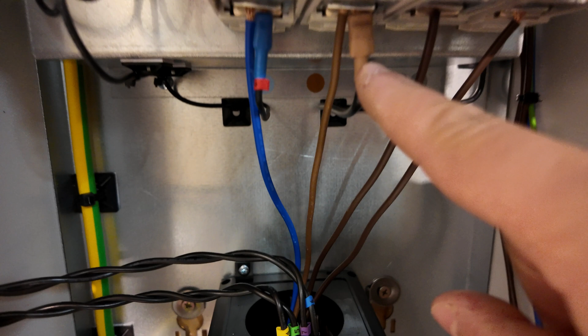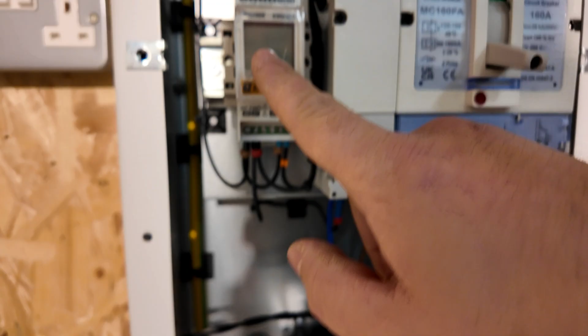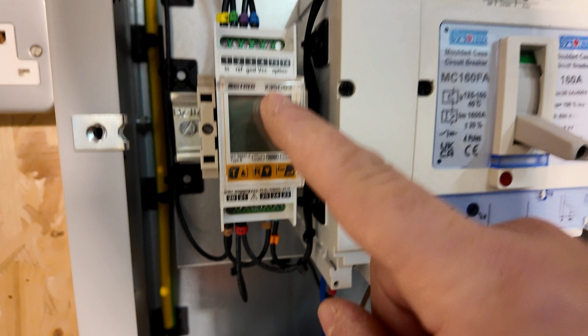Now you can see off the bottom of here we've got a line and a neutral running into the side of the MCCB. Those tie away and run off to this RCD monitoring module, where we can make settings for what we want our RCD trip currents to be and how they behave. In essence, when that sees some earth leakage, it can operate this MCCB. You can see there's a couple of fly leads running across the top here, and they drop back down into this as well - these are taking power off to this actual unit to power it.